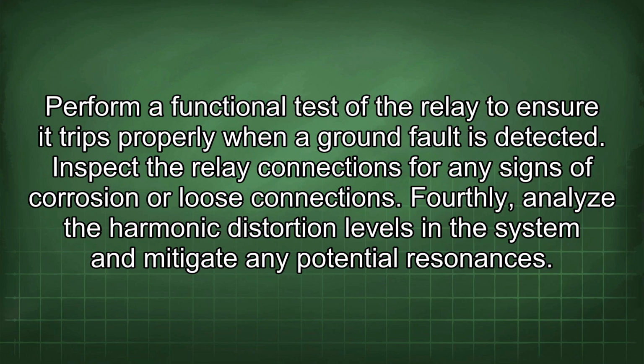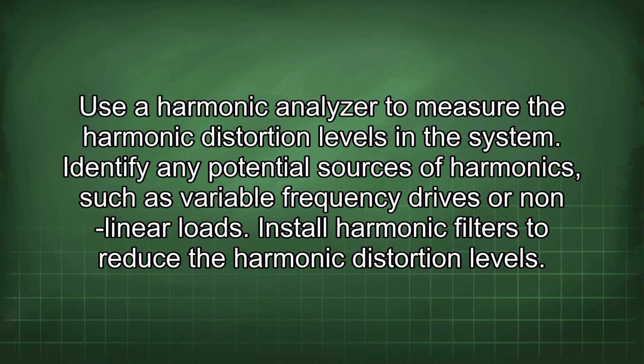Fourthly, analyze the harmonic distortion levels in the system and mitigate any potential resonances. Use a harmonic analyzer to measure the harmonic distortion levels in the system. Identify any potential sources of harmonics, such as variable frequency drives or nonlinear loads. Install harmonic filters to reduce the harmonic distortion levels.